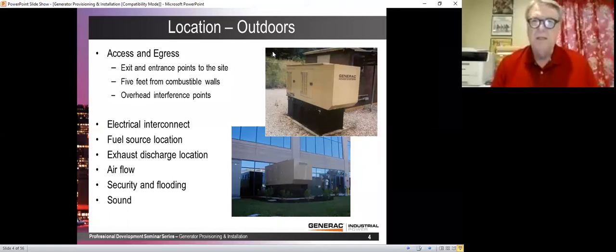But it's actually a little more complicated than that. First of all, the 5 feet is from combustible walls and building openings. So if you're near a non-combustible wall, then that 5 foot does not apply. Also, the generator cannot be installed underneath a building opening or underneath an air intake to a building. That's a not too common mistake, but fairly common because you don't look for the air intakes when you're siting the generator.